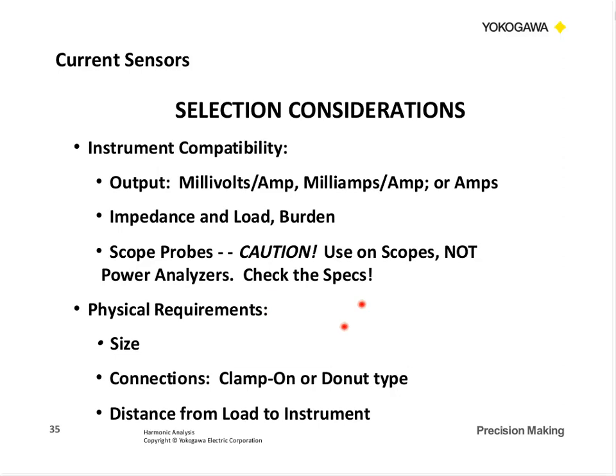Then, of course, how are you going to use it? The physical requirements, size can be a factor sometimes. Do you need a clamp on, or can you use a donut type, feed the cables through the donut hole? The other thing to consider is the distance from the load to the instrument. And this can be a burden on the CT. If you've got questions, we can always help you with that selection.